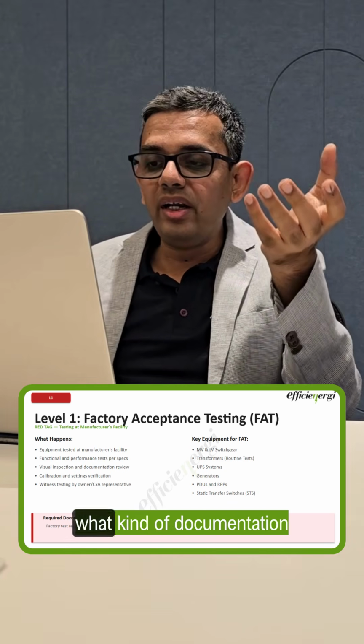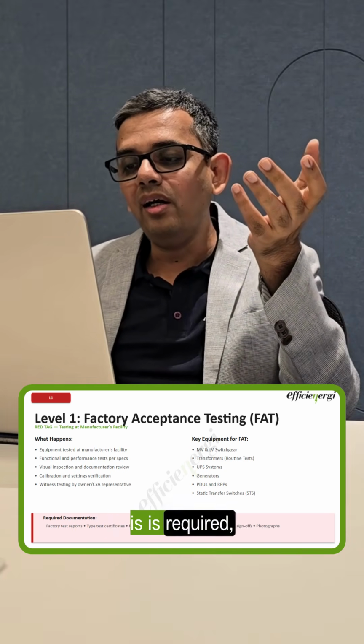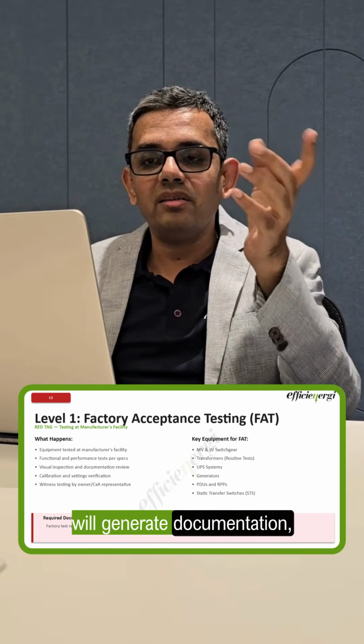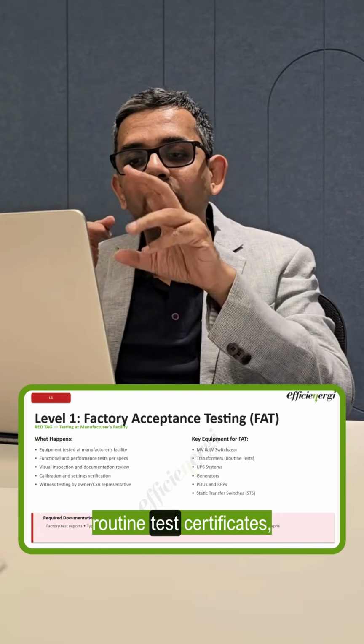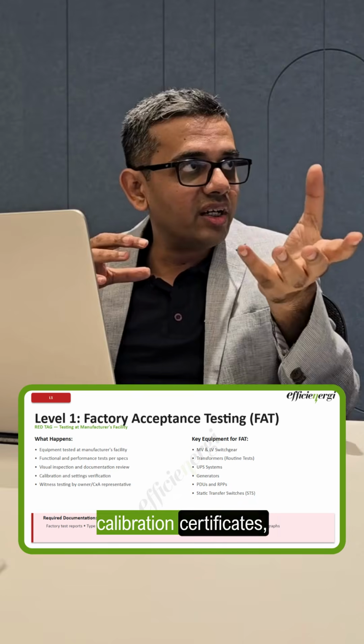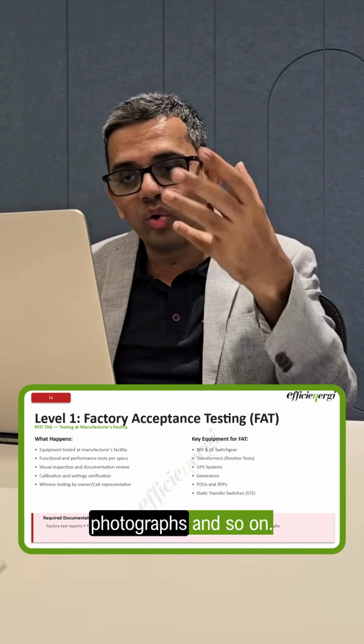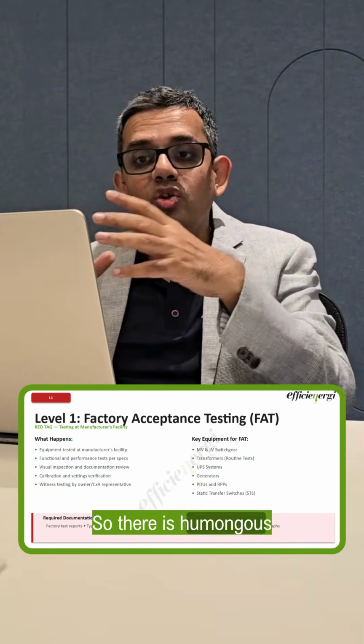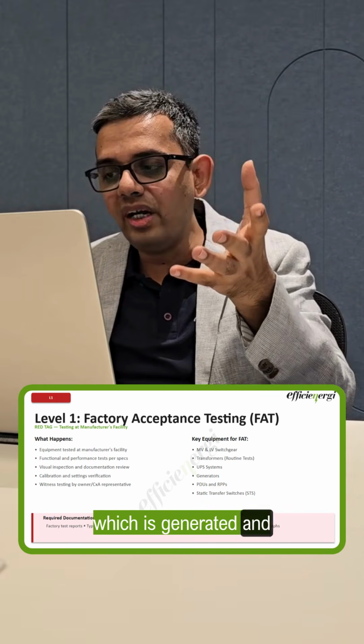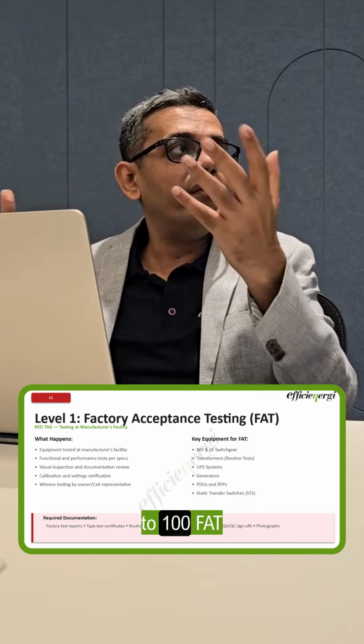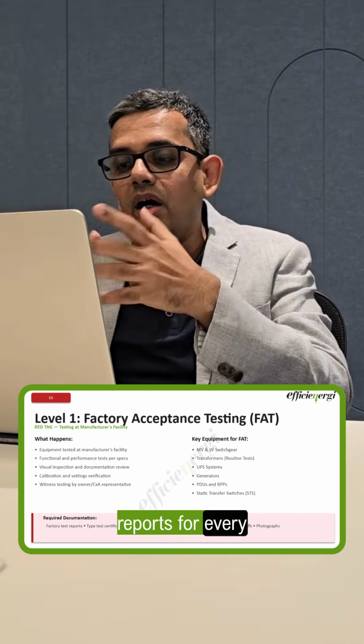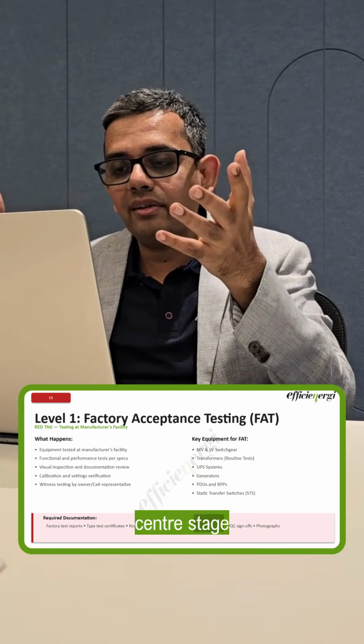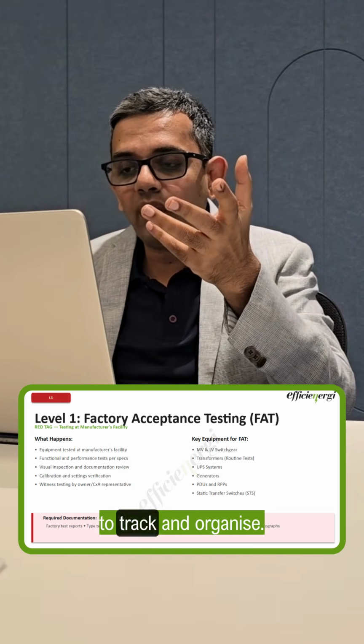During the FAT, what kind of documentation is required? Each test generates documentation: factory test reports, type tests, routine test certificates, calibration certificates, QA/QC sign-offs, photographs, and so on. There's a huge amount of documentation generated, and you might have 50 to 100 FAT reports for every data center stage that you'll have to track and organize.